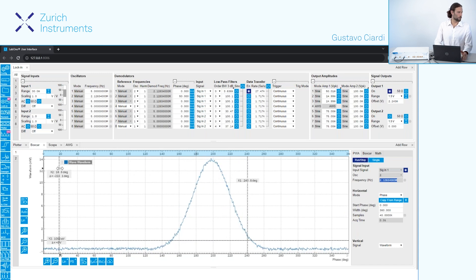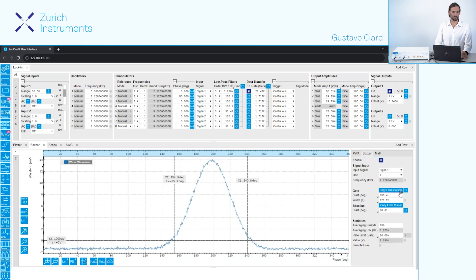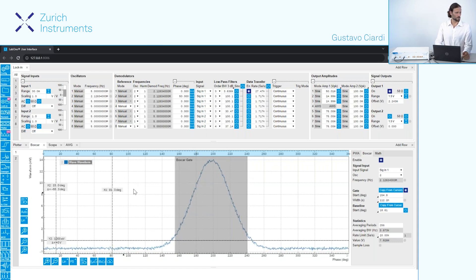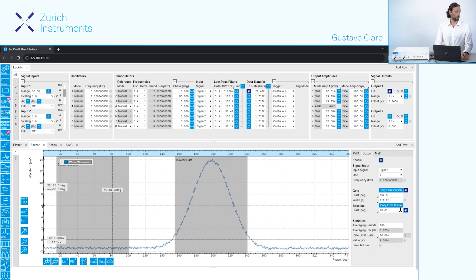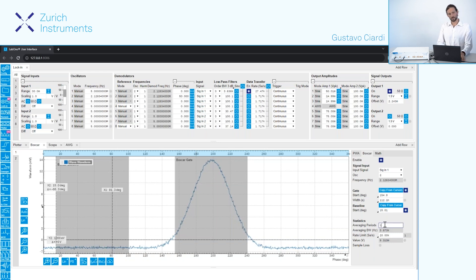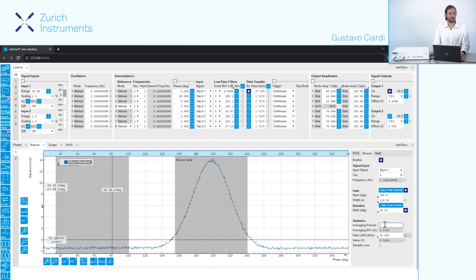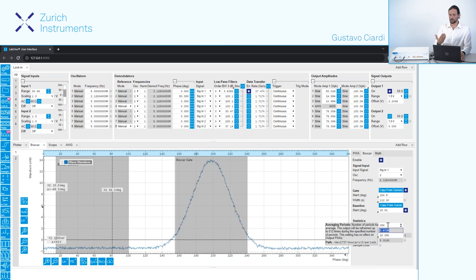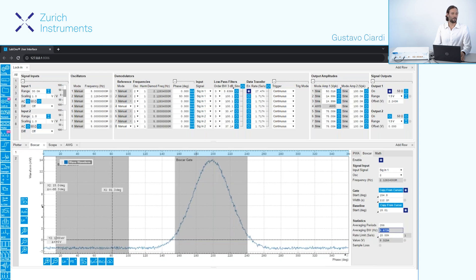Going back to phase and running again, we can now perform our boxcar averager measurement. We set the boxcar averager window around my signal — copy from cursors, activate the boxcar gate — and we also set the baseline window somewhere where there is no signal, in order to subtract the boxcar baseline. The other parameter we set is the averaging periods. Here we are using 256 gates before sending out the results, which is sometimes known as gated integration. This translates into an averaging bandwidth defined by both the averaging periods and the repetition rate of the signal.